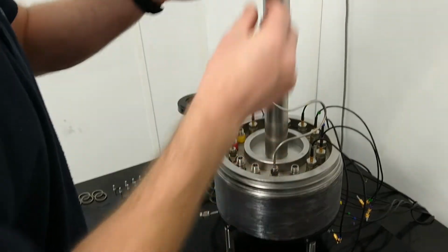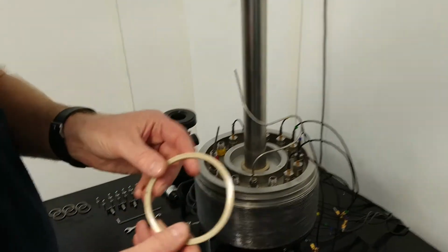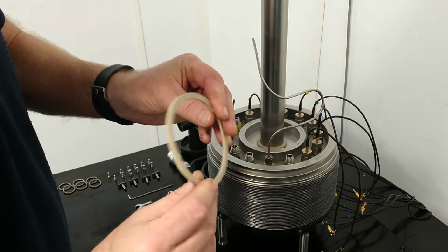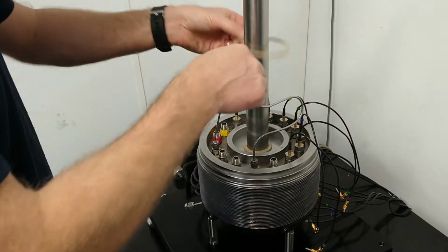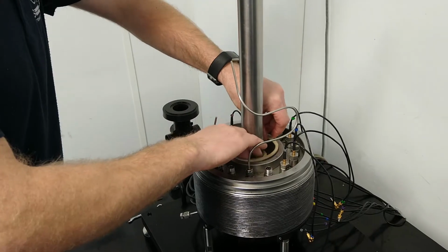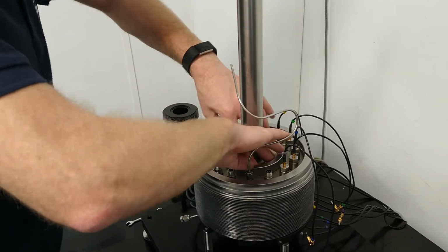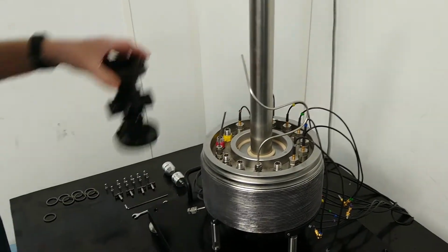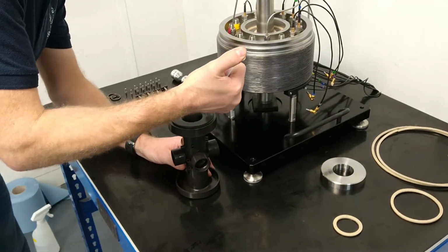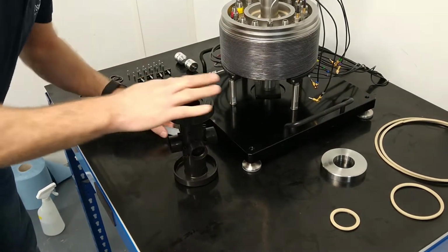Slide one of the small fixed rings down the assembly aid with the chamfered edge facing upwards. Now place one of the larger rings with the chamfered edge facing upwards into the center section of the cell base. Ensure this is located flat against the sample ring. Apply silicone grease to all sealing surfaces of the sample membrane, top and bottom.